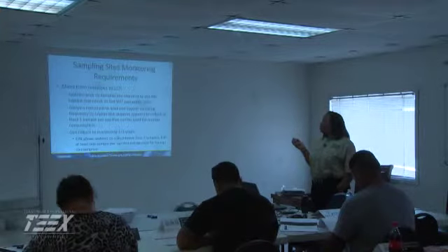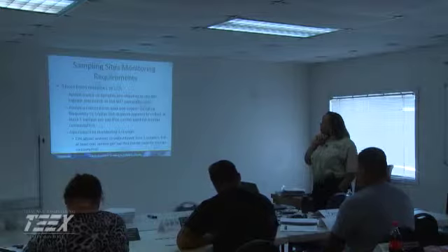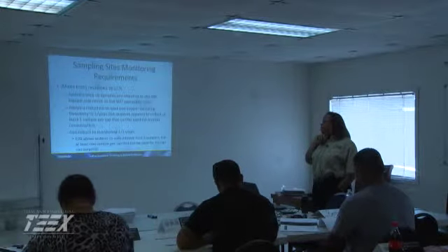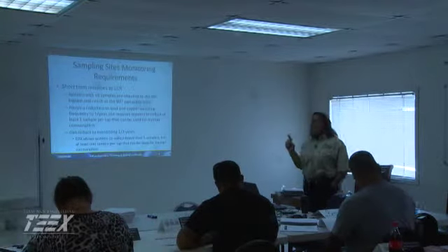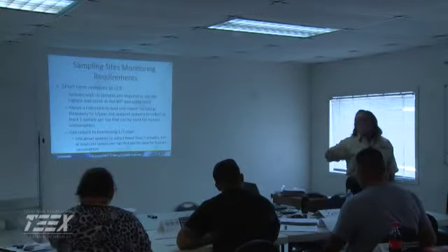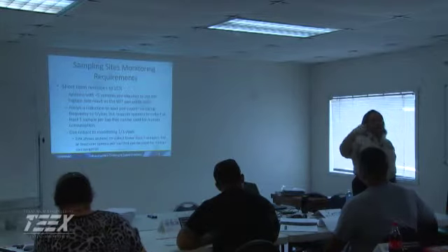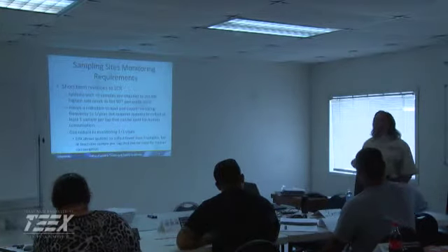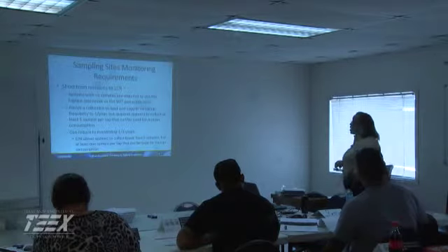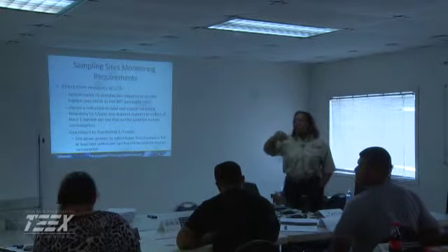The other amendment in 2007 allows for reduction of lead and copper sampling frequency to 1 per year. And that is if all of your lead and copper came out below the 90th percentile. So instead of twice a year or every 6 months, you have the right to reduce to once a year. Are you all doing any once a year? Or are you still doing the semi-annual?